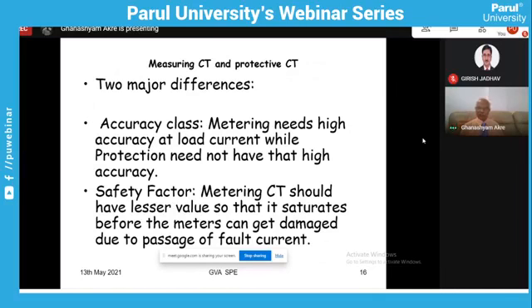While in the case of a current transformer for metering purposes, if 20 times current flows during the fault, then the meter may get burned, because it is not rated for 20 amperes. The meters are delicate and they may burn, they may get damaged, or their accuracy will go. So in that case, the metering CT should be inherently made in such a way that it will not faithfully reproduce the primary current in the secondary. That means it should saturate. So generally, when you are passing 20 times current in the primary, the secondary should have 2 or 3 amperes maximum, so that the meter will not get damaged.